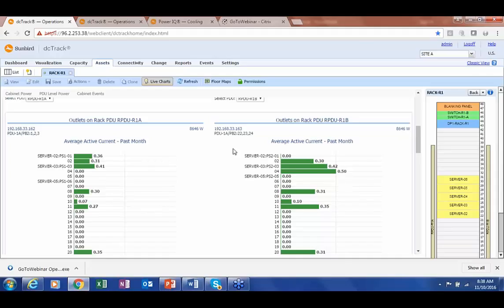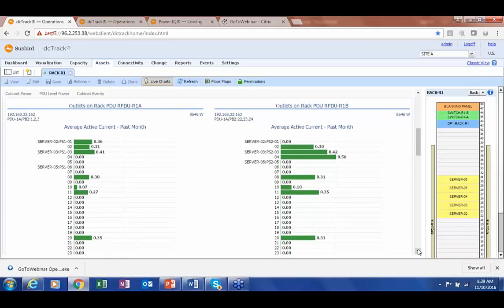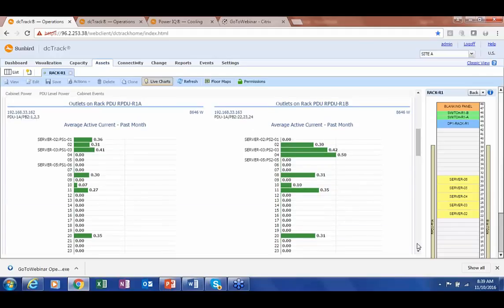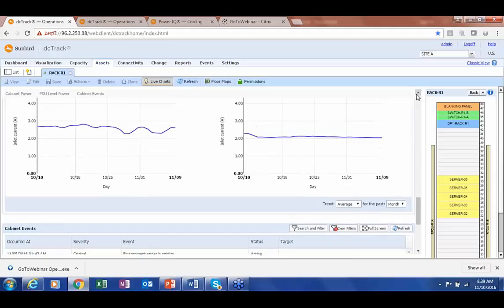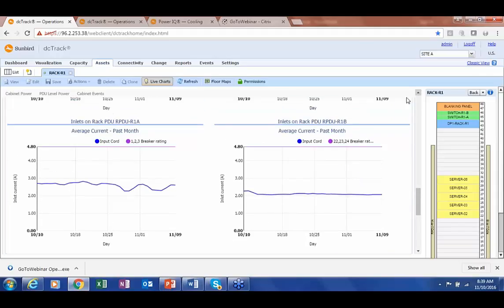Further drilling down to the cabinet, once I'm looking at the cabinet loads and measured values, I can look rack PDU by rack PDU in a true side-by-side analysis, outlet to outlet, as well as look at line charts that reveal my power consumption relative to breaker rating. So here is the load on my input cord to my rack PDU, and how it compares to my breaker, defined as breakers 1, 2, and 3. You have an easy at-a-glance view where this upper purple line represents the capacity at 4.8 amps, and the blue line represents the actual load at 2.54 amps.